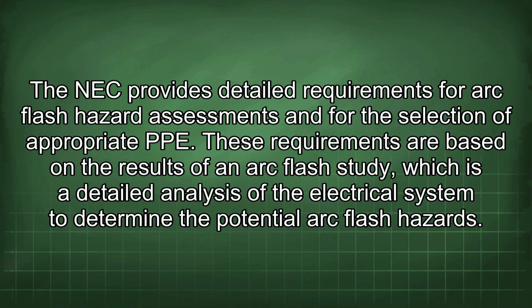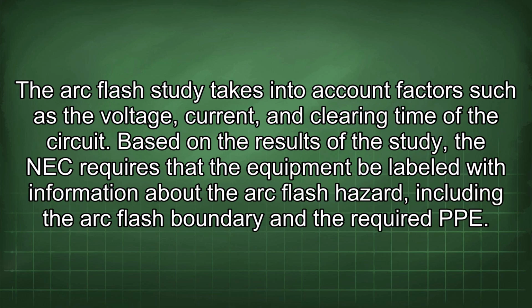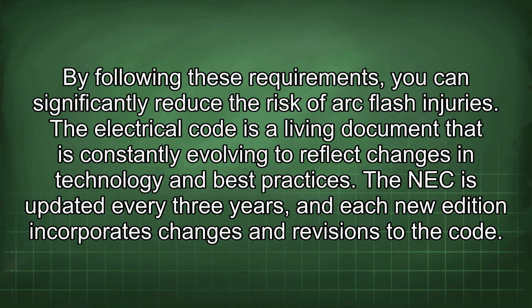These requirements are based on the results of an arc flash study, which is a detailed analysis of the electrical system to determine the potential arc flash hazards. The arc flash study takes into account factors such as the voltage, current, and clearing time of the circuit. Based on the results of the study, the NEC requires that the equipment be labeled with information about the arc flash hazard, including the arc flash boundary and the required PPE. By following these requirements, you can significantly reduce the risk of arc flash injuries.